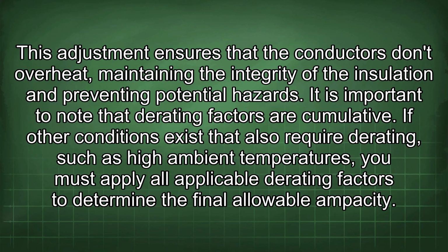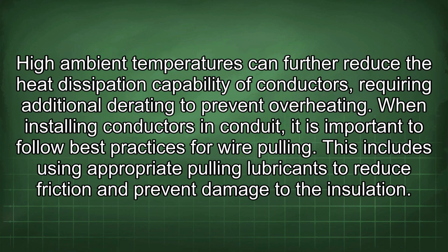It is important to note that derating factors are cumulative. If other conditions exist that also require derating, such as high ambient temperatures, you must apply all applicable derating factors to determine the final allowable ampacity. High ambient temperatures can further reduce the heat dissipation capability of conductors, requiring additional derating to prevent overheating.